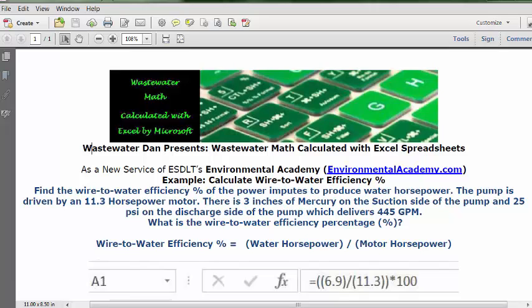Today's problem reads: Find the wire-to-water efficiency percentage of the power inputs to produce water horsepower. The pump is driven by an 11.3 horsepower motor. There is 3 inches of mercury on the suction side of the pump and 25 psi on the discharge side of the pump which delivers 445 GPM.